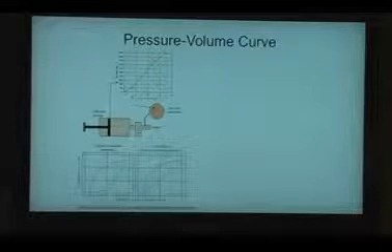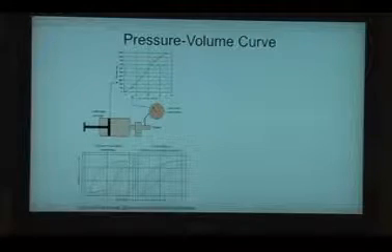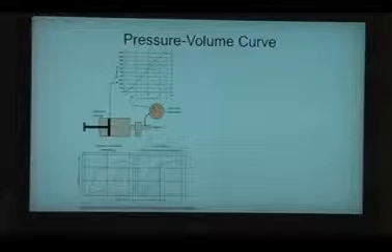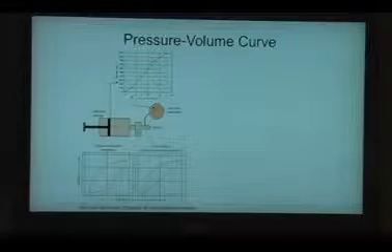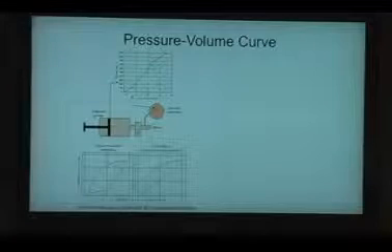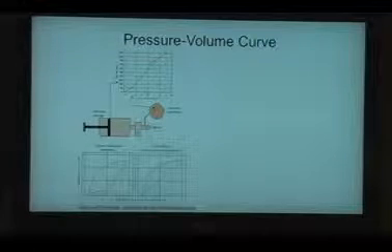I used to remember, and I'm not going to mention any names, these are physicians who aren't here anymore anyway, but when we were enthusiastic about PV curves a couple of years ago, I would go into the MICU and some well-meaning intensivist had the therapist change the ventilator to the pressure volume curve so that on rounds they could see where to set the peak. Problem was the patient's on pressure support. That invalidates the whole thing.